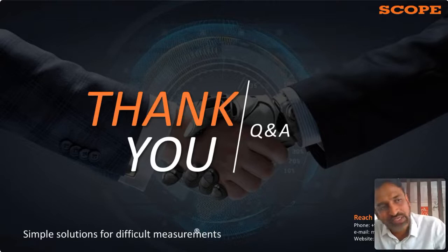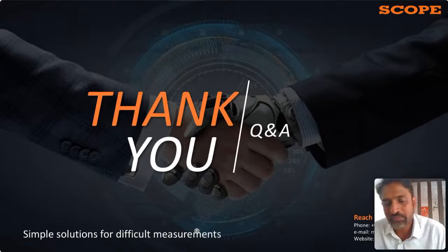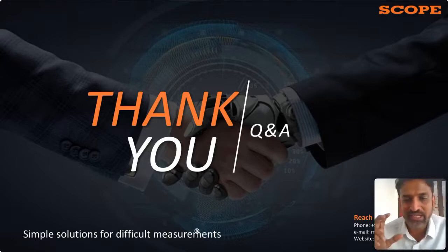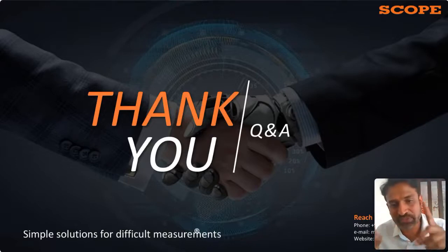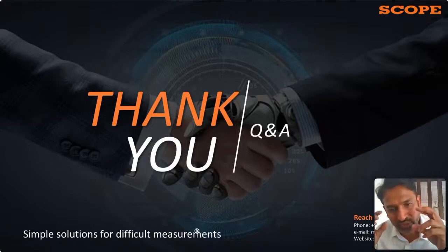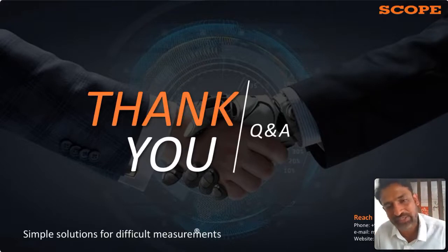With a BCU also, you can collect digital inputs from the breaker, isolator and switch, and energy data directly from the CTPT. But here the key point is that it is very limited in protocols. In a BCU, you have only either the 61850 protocol or some Modbus protocol, not more than that. But visualization is better, because the BCU has a bigger screen where you can go inside and see all the parameters, all the functions within the BCU.